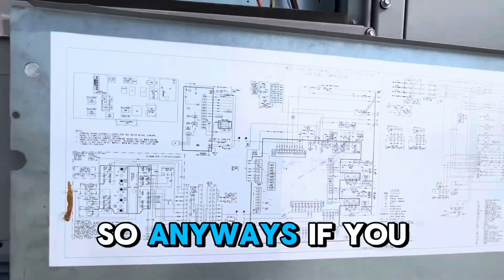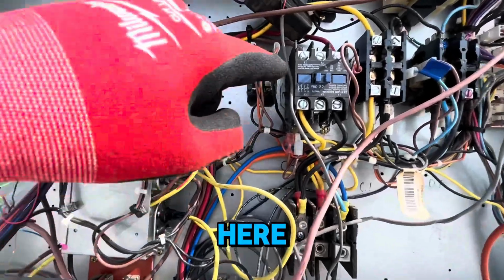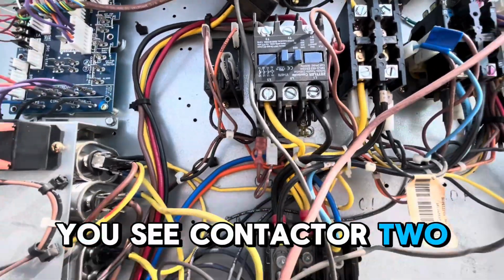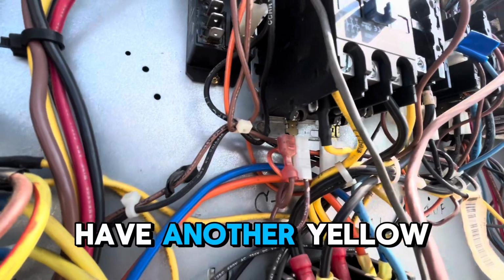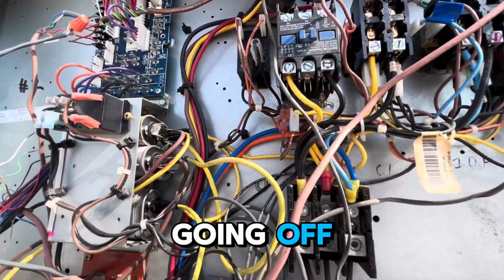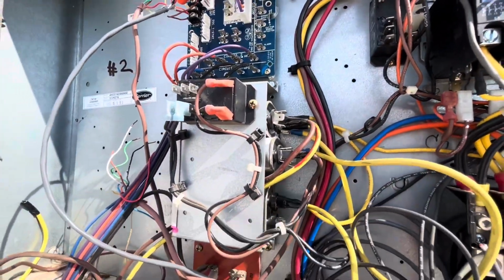So anyways, if you look at it up here, you see contactor 2, black, yellow, and then you have another yellow going off and probably going over here to your condenser fan motors.